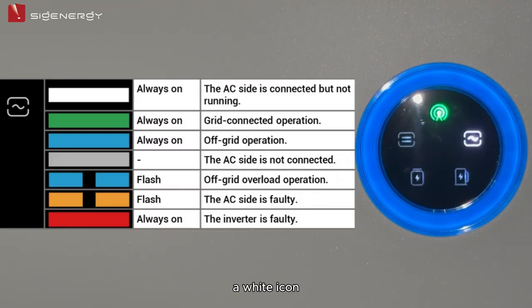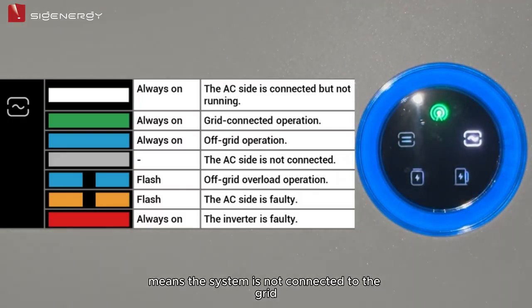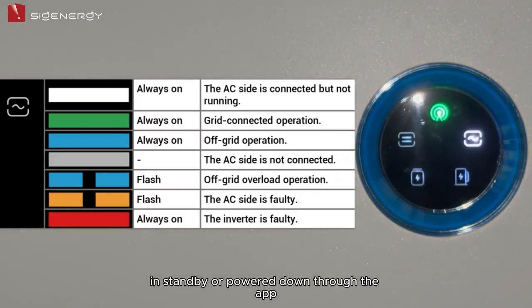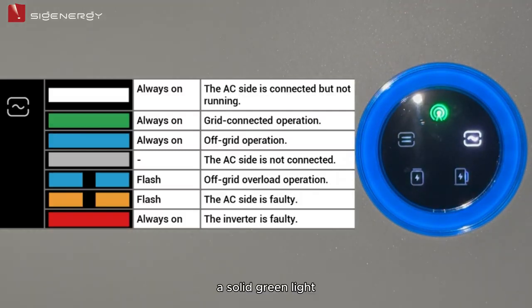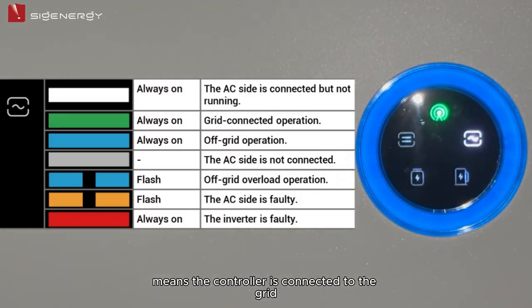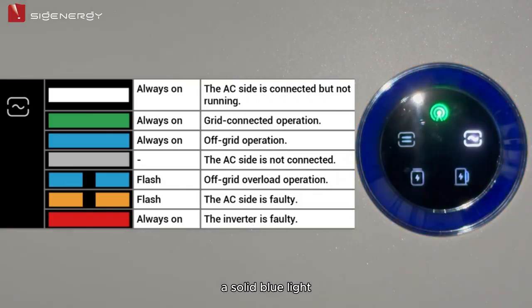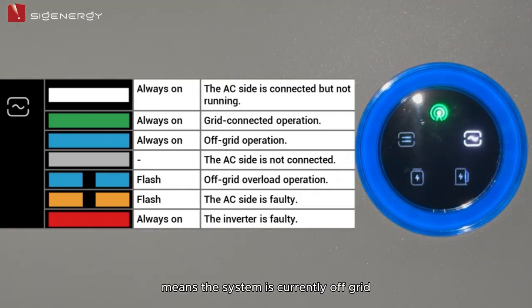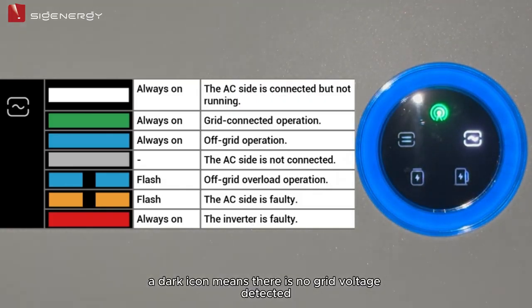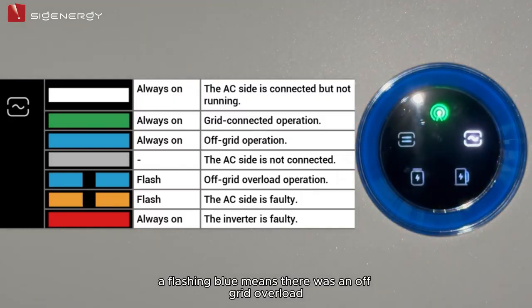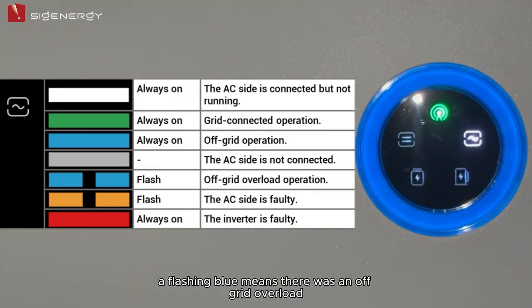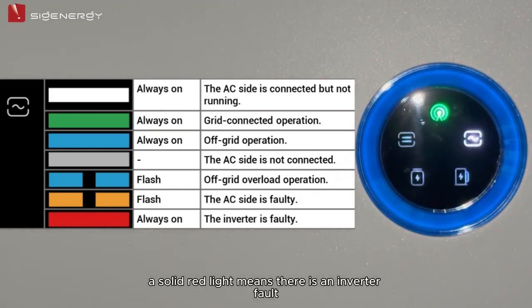Starting at the top, a white icon means the system is not connected to the grid, in standby, or powered down through the app. A solid green light means the controller is connected to the grid. A solid blue light means the system is currently off-grid. A dark icon means there is no grid voltage detected. A flashing blue means there was an off-grid overload. A flashing orange light means there is a grid fault. A solid red light means there is an inverter fault.